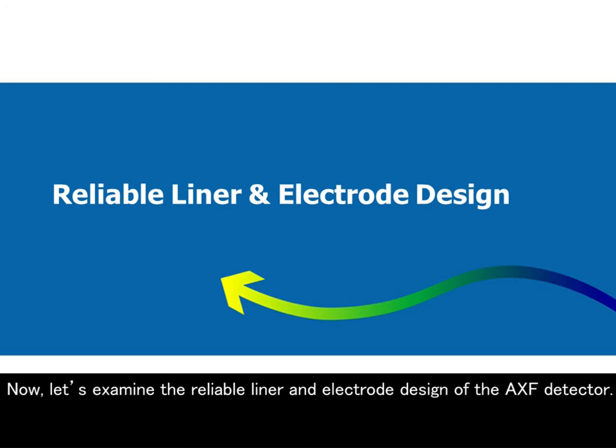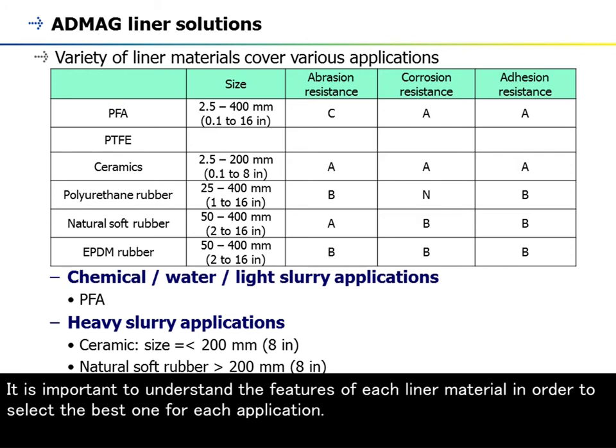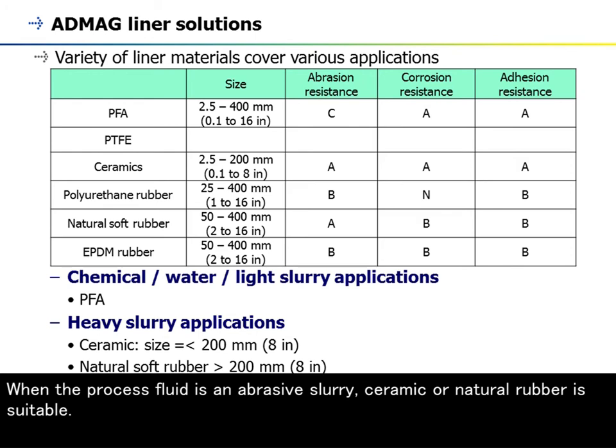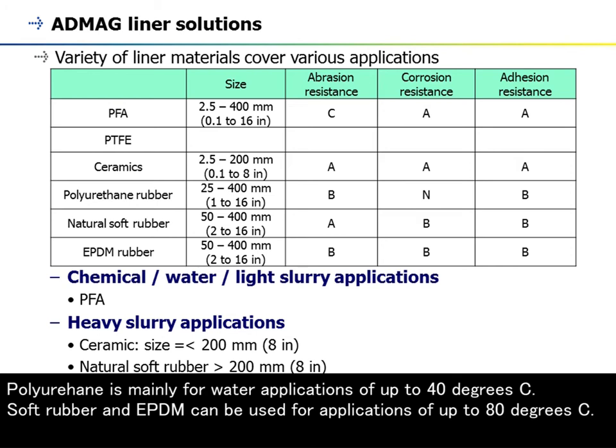The ADMAG AXF has a wide selection of liner materials. It is important to understand the features of each liner material in order to select the best one for each application. PFA has very good corrosion resistance and offers wide coverage such as for chemical, water, and light slurry applications. When the process fluid is an abrasive slurry, ceramic or natural rubber is suitable. Natural soft rubber is the major liner material in large size slurry processes and the mining industry. Polyurethane is mainly for water applications of up to 40°C. Soft rubber and EPDM can be used for applications of up to 80°C.